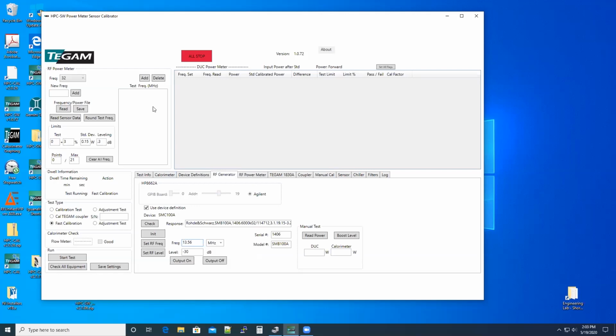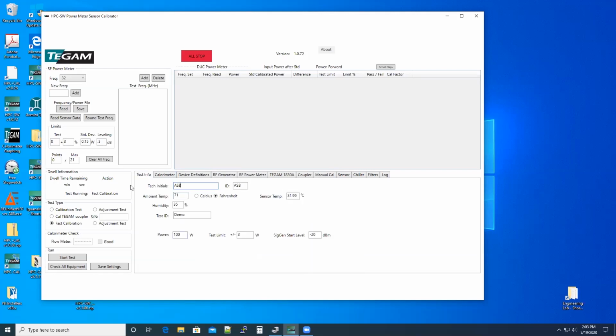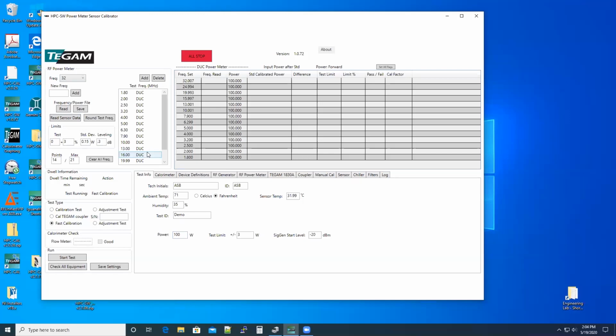So now we need to define our test. We put in some record keeping information like my initials, the temperature, the test ID, but most importantly, what power do we want to calibrate at? I'm going to do a test today at 100 watts. The test limit is plus or minus 3 watts, because the Bird 4421 is a 3% sensor. And let's go over here to the read the sensor data button and populate the frequency list. So we've sent a query to the power meter to ask the sensor what its frequency data is. You see we've got 14 points out of a possible 21 that are in the sensor.